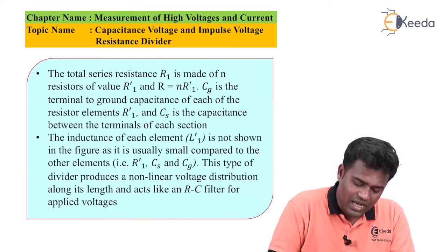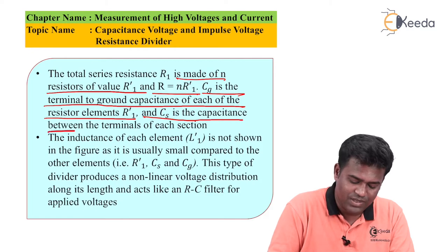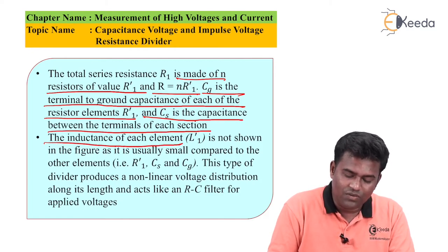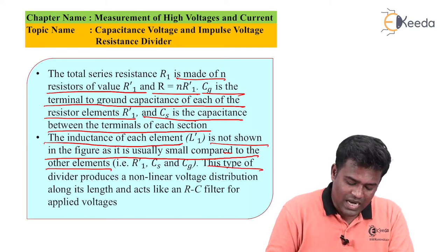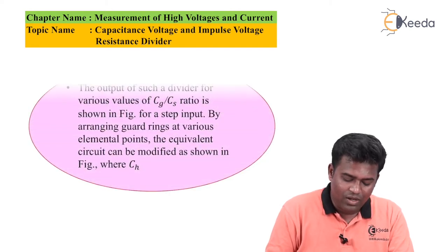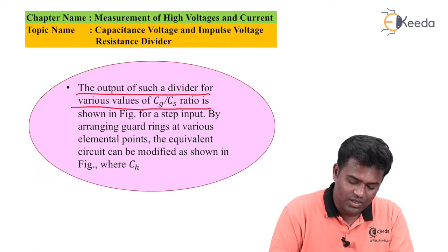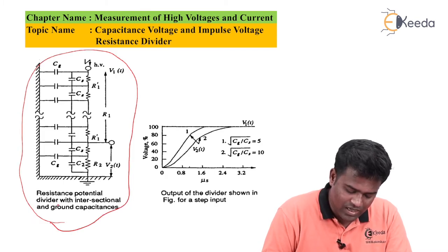The total series resistance R1 is made of resistance of value R1' where R = N × R1'. Cg is the terminal-to-ground capacitance of each resistance element R1', and Cs is the capacitance between terminals of each section. The inductance of each element is not shown as it is usually negligible compared to other elements. This type of divider produces a non-linear voltage distribution along its length and acts like an RC filter for applied voltages.